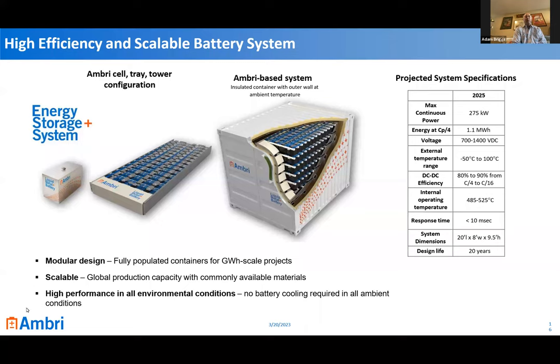In a 20-foot container, we have about 1.1 megawatt hours of energy, up to 275 kilowatts of power, and a strong efficiency of about 80 to 90%, depending on how it's used. It also has instantaneous power capability, going from zero to full power in less than 10 milliseconds.